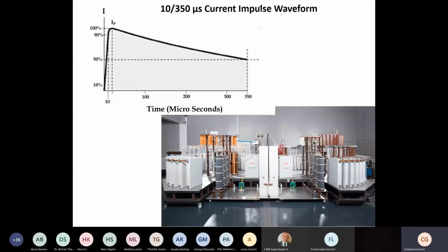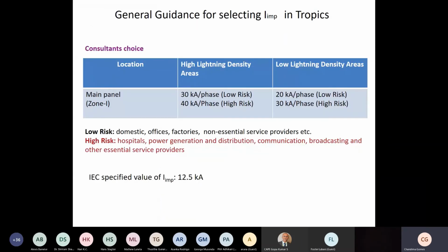When you apply this current into the SPD, what is the maximum current that SPD can withstand? This is the capacity or the specification of this current. And now I'm giving you some idea, especially for the tropics. We are coming to a little strategic point now. IEC specifies an IIMP of 12.5 kiloamperes.